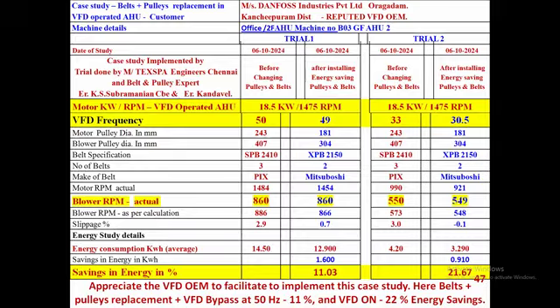Basically, they are VFD majors, OEMs, but they are also surprised to see what we are able to achieve. In the case study, the blower RPM was fixed at around 860 before, at 50 Hertz, and at 33 Hertz it is around 550 RPM. The energy savings from just the belt and pulley changes for a given motor to blower gave around 10%, and the VFD, by voltage reduction, gives around 10%. Around 22% savings is possible at a cost of less than 20,000 only.